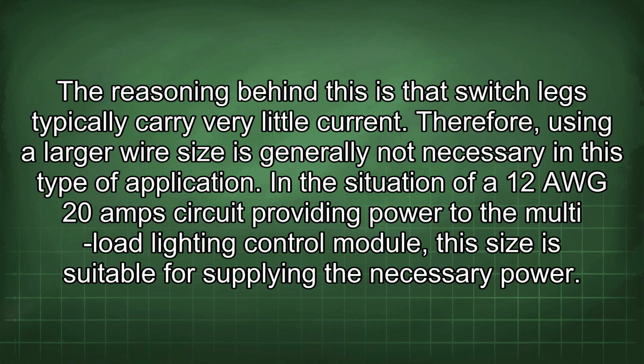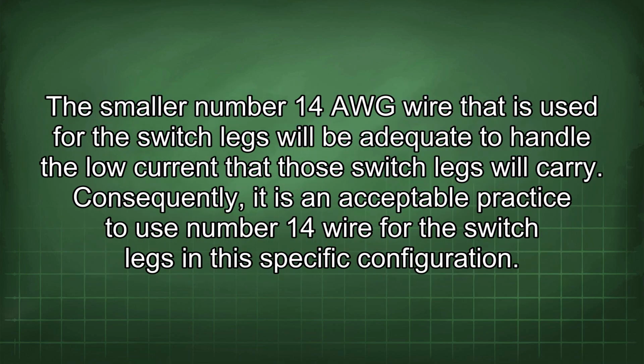In the situation of a 12 AWG 20 amp circuit providing power to the multi-load lighting control module, the size is suitable for supplying the necessary power. The smaller number 14 AWG wire that is used for the switch legs will be adequate to handle the low current that those switch legs will carry. Consequently, it is an acceptable practice to use number 14 wire for the switch legs in this specific configuration.